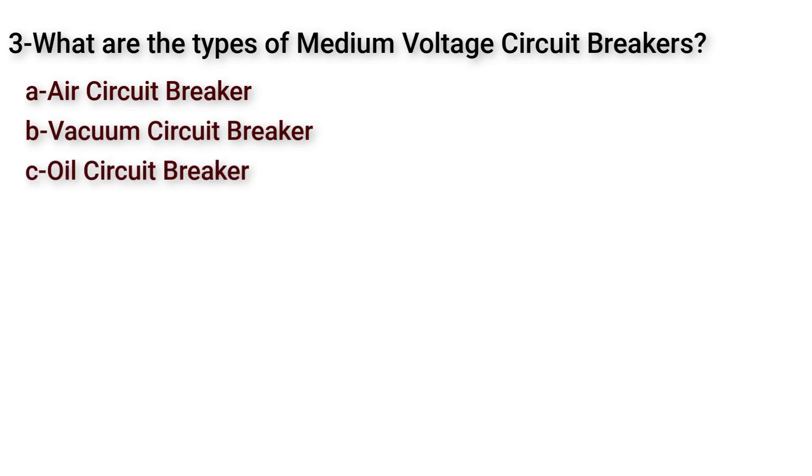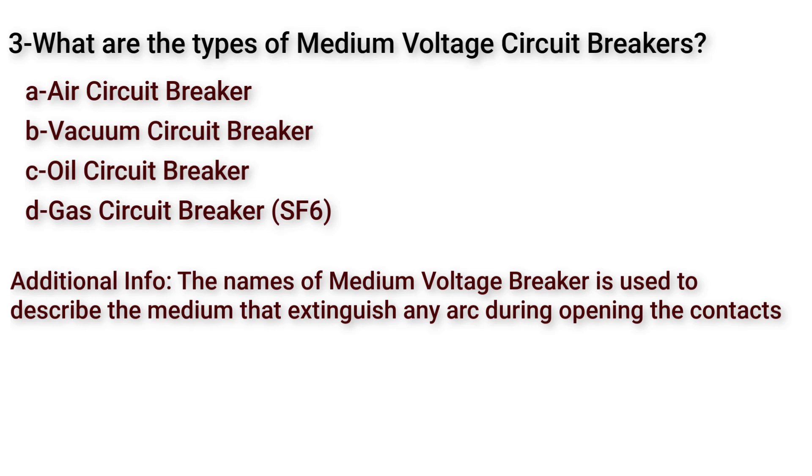The answer is air circuit breakers, vacuum circuit breakers, oil circuit breakers and at last gas circuit breakers which use SF6 gas. As you can see here we call the breakers on these names to describe the medium we use with the contacts to extinguish the electric arc during opening the contacts.